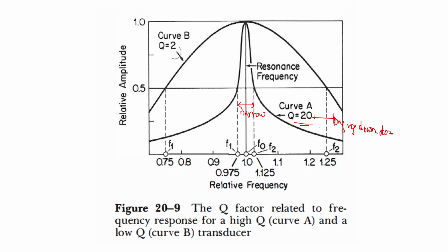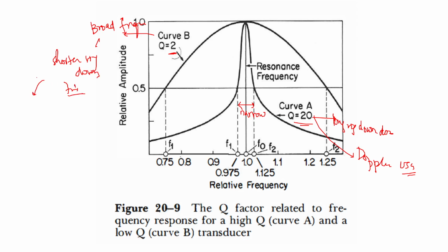And this type of system, where Q is more, is used for Doppler systems, Doppler ultrasound transducers. Whereas this is curve B, which has a broader frequency range. This broader frequency, that is Q equal to 2, gives a broader curve, and this broad frequency range has a shorter ring down time. The ring down time is shorter, and as a result this is mainly used in organ imaging, that is pulse echo operation.